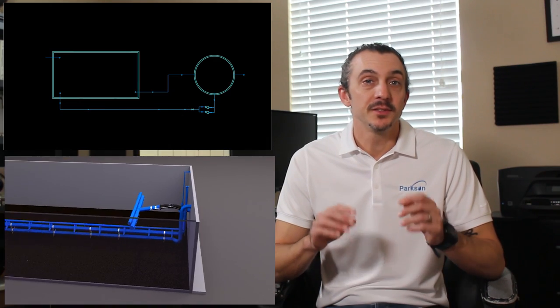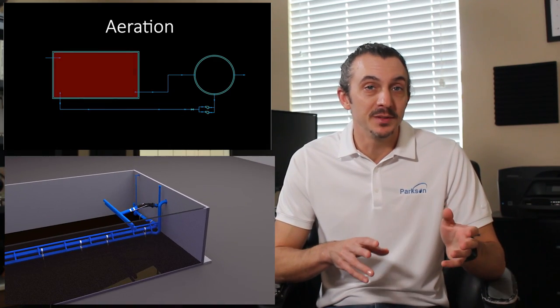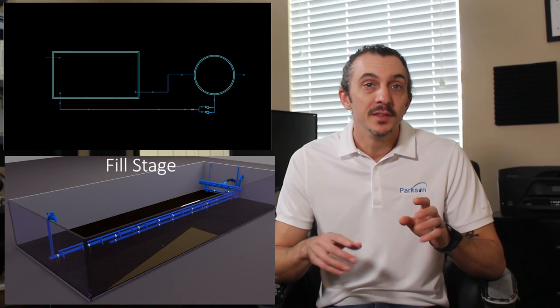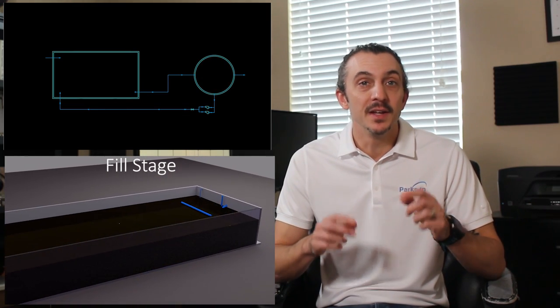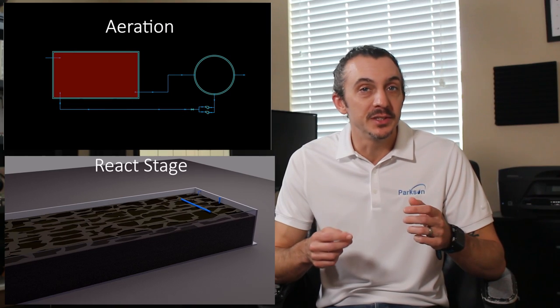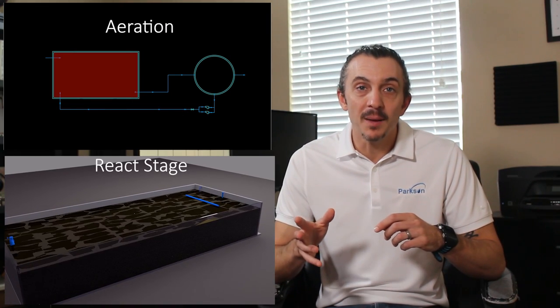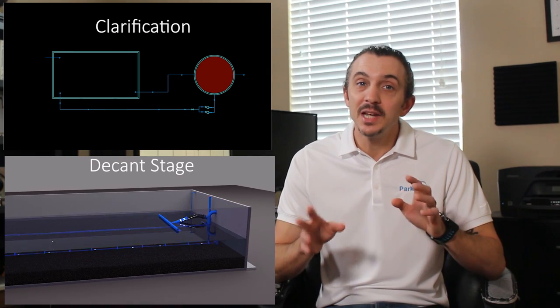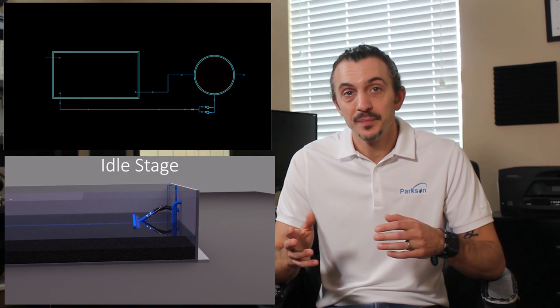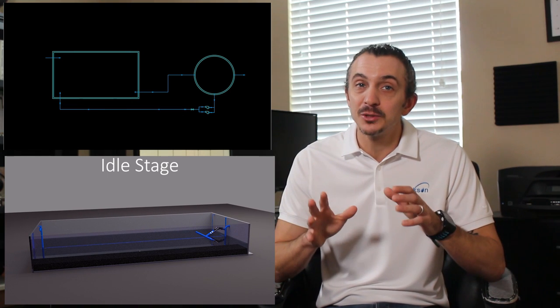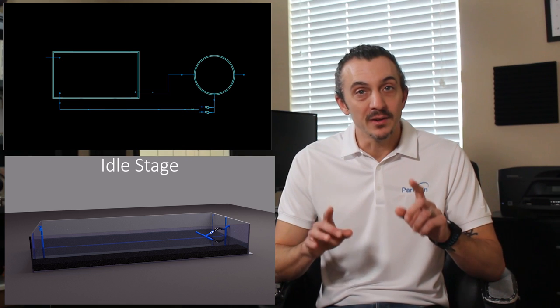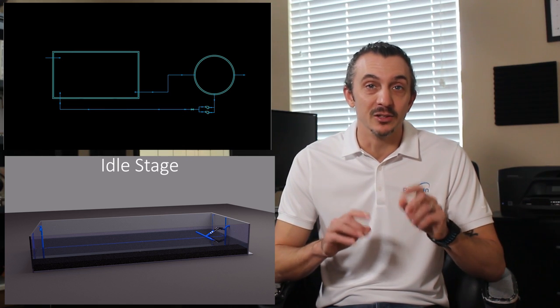For a single-stage process, traditionally we'd have an aeration tank followed by a clarifier. In an SBR, the tank would fill up initially, then air would be added for the aeration step. Then the air would stop and it would settle and decant the water off the top, which is the same thing happening in the clarifier. If we wanted to use the same single-stage plant for biological nutrient removal, well, we're out of luck — we'd have to tear it down and build something that looks like this.